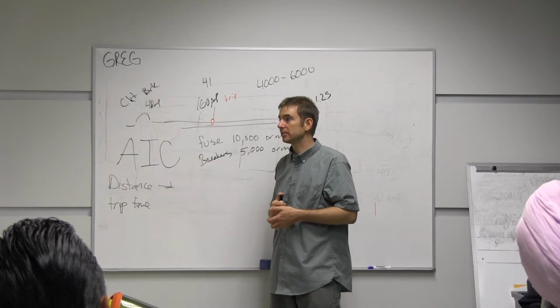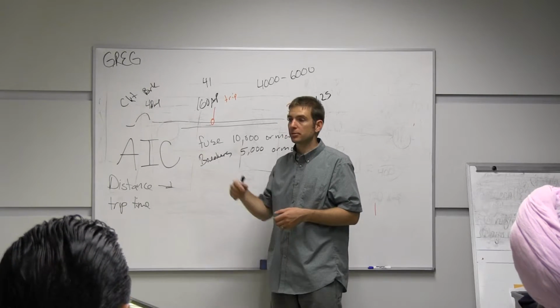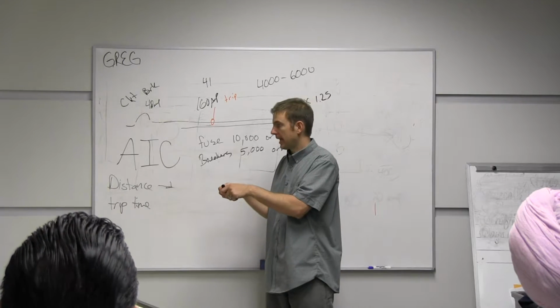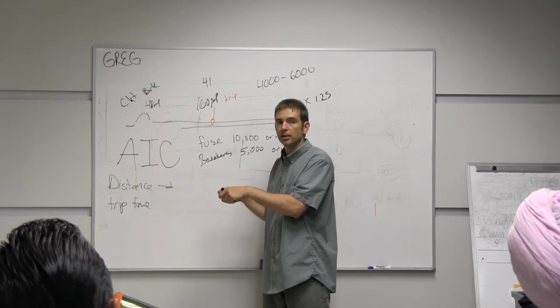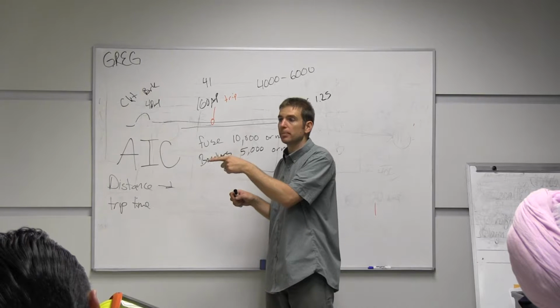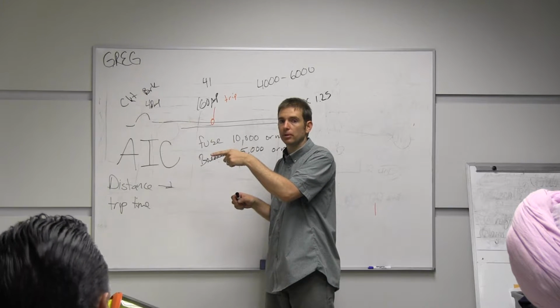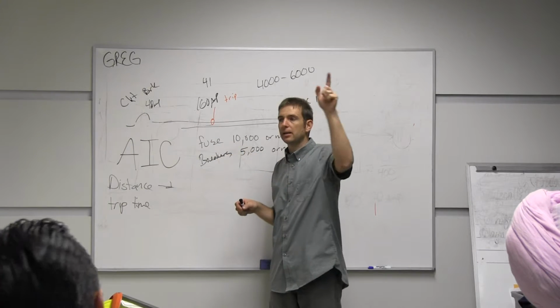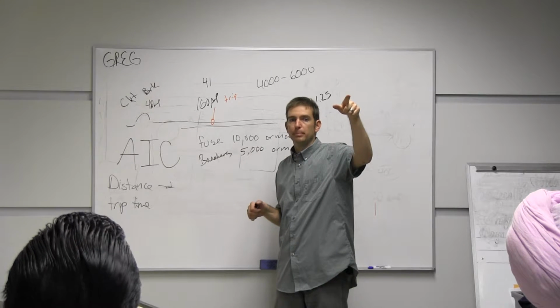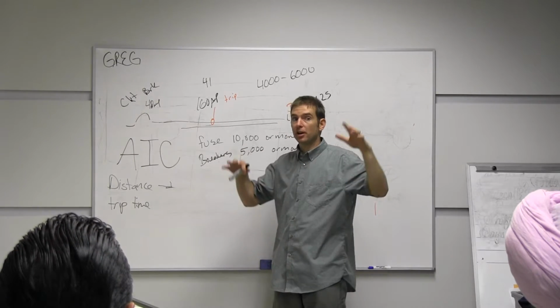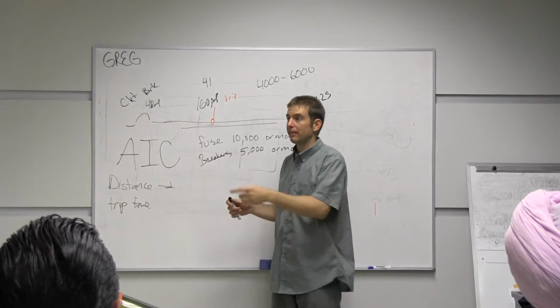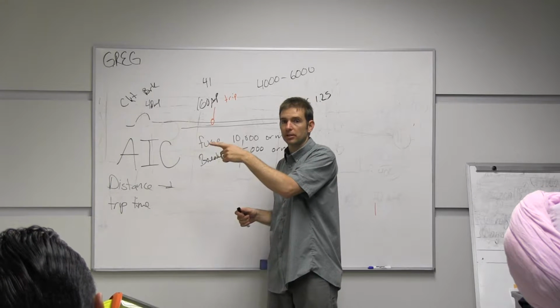Sometimes it's a bad thing, because let's say I'm here working on this receptacle, and I accidentally touch the hot wire to the box, and instead of tripping the circuit breaker to that receptacle, I trip the main breaker at a panel somewhere. I don't want to turn off power to the building. If it trips, I want to just trip the circuit breaker to that circuit.